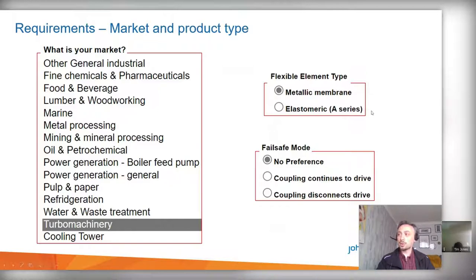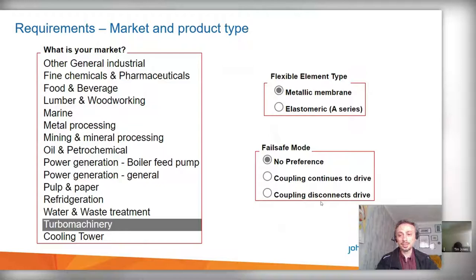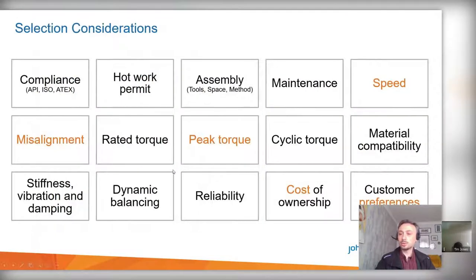For flexible element type, you can have a metallic membrane or an elastomeric element. Elastomers provide damping characteristics but wear out and typically need replacement within a year. Metallic membranes can operate over 30 years, sometimes 50 years if properly selected and designed. Fail-safe features can also be specified — for example, a diaphragm coupling can be designed to disconnect upon failure: when it reaches a failure point, the product shears and stops transmitting torque, but all parts can still rotate for a certain number of cycles.